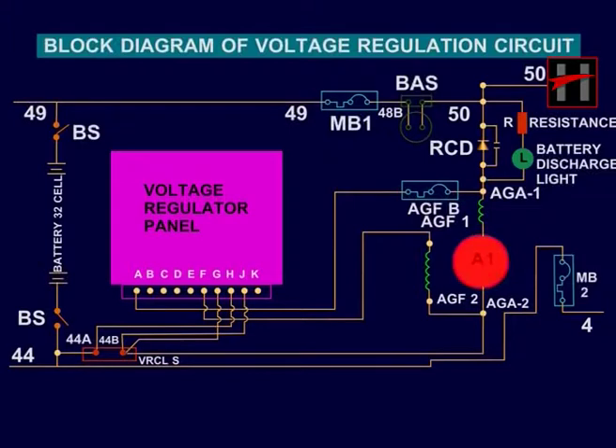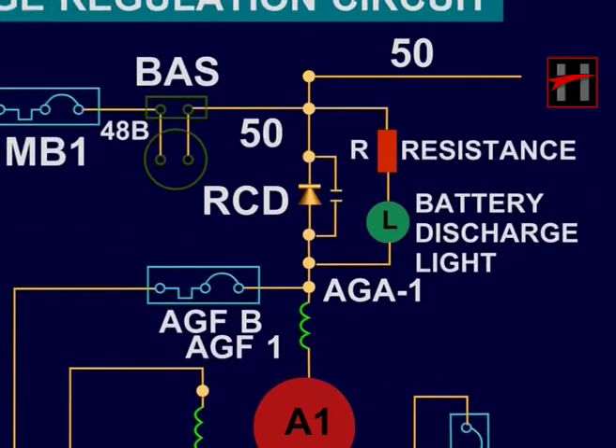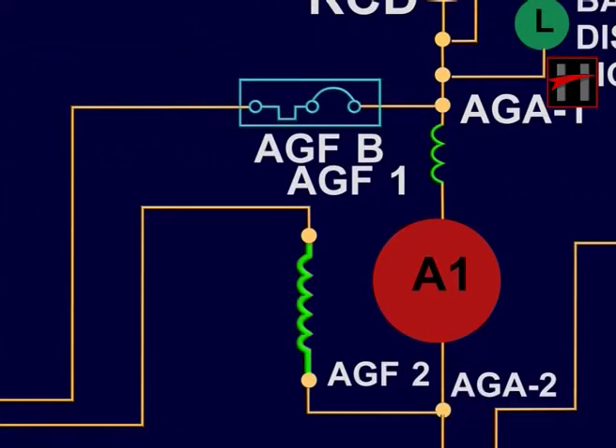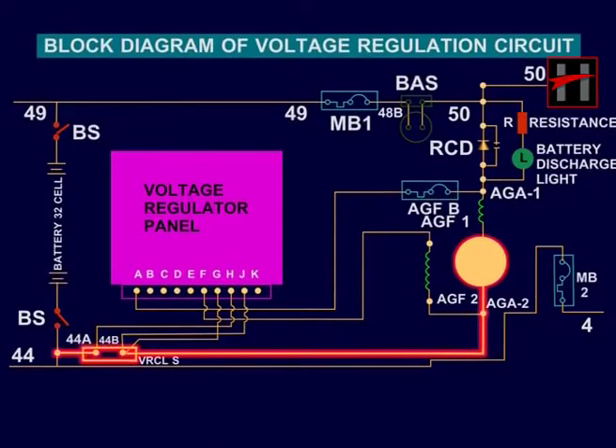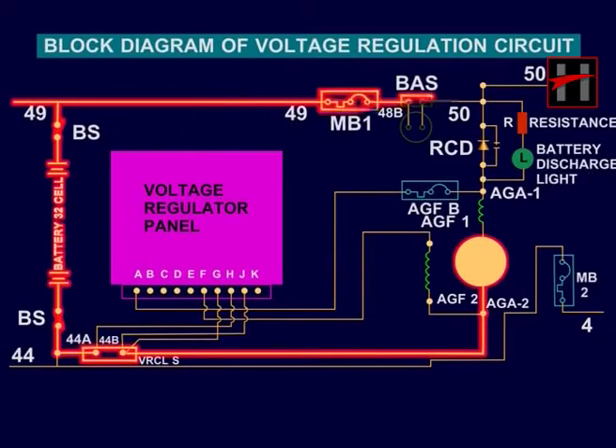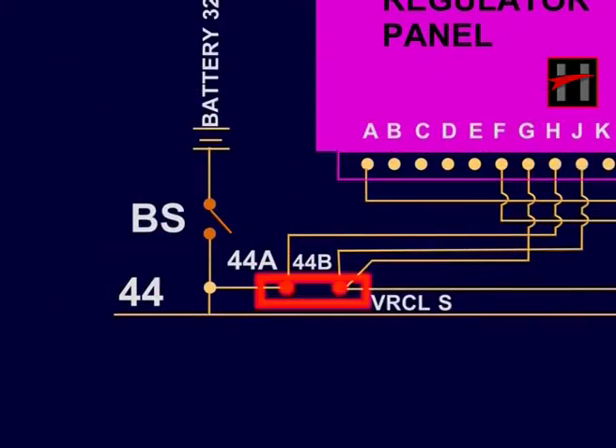The auxiliary generator is connected between cable number 50, RCD, AGF2, VRC-LS to cable number 4. The RCD prevents the discharge of the battery into the auxiliary generator when the AG is not working. The feedback from VRC-LS is connected to VRP for load current control.